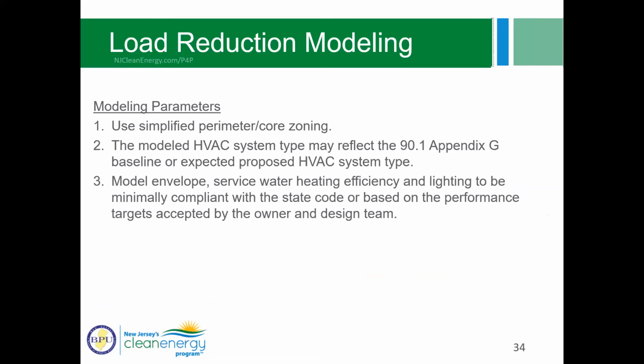When you do your load reduction modeling, and similar principles apply to the simple box and the conceptual design modeling as well, you want to use simplified perimeter core zoning. For the modeled HVAC system type, you can either use the 90.1 Appendix G baseline or your expected proposed HVAC system type. And you want to model the other parameters, like envelope, service water heating efficiency, and lighting, to be minimally compliant with the state code, or, let's say the owner has targets for these, then you can use those as well.